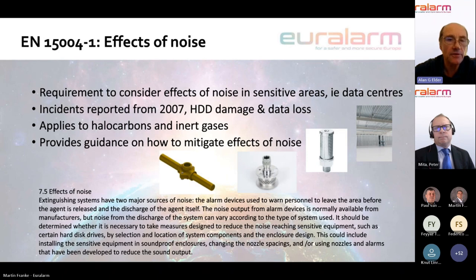Contrary to some belief that this only applies to inert gases, it also applies to the halocarbons as well. It is all about the noise that is generated during the discharge of a system. It is not only the gas and the noise of the discharge of the gas, it can also be the alarm devices that are within the protected space. And what the new edition of the standard does, and I've repeated the whole of the clause there, it says that the effects of noise can be the alarm devices, which are used to warn personnel to leave the area before an agent discharge, and the discharge of the agent itself.